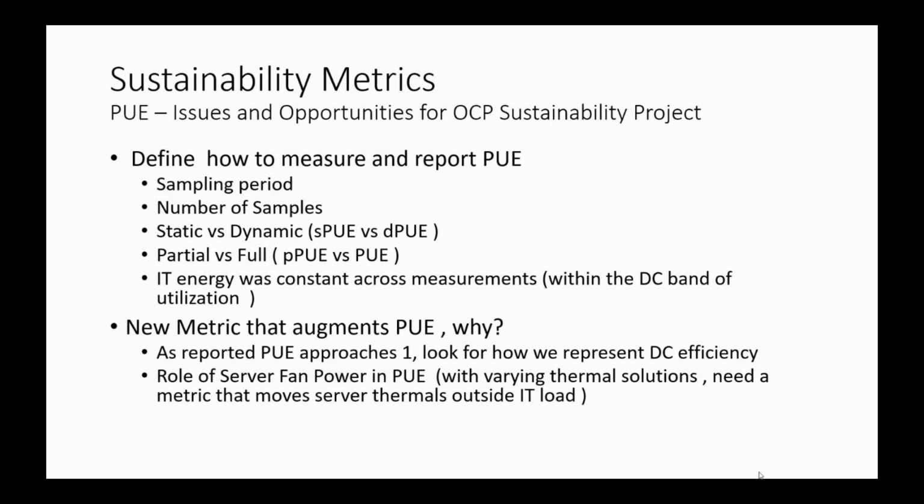If it's, let's say, over a month, did you take 10 samples in that month, or did you just take one sample? And we'll talk about static versus dynamic, which is, did you do a spreadsheet analysis or did you actually measure this thing? And then, are you reporting, because it's supposed to be a data center metric, and what is a data center is a good thing to define, right? Otherwise, what you're getting is truly a partial PUE, right?